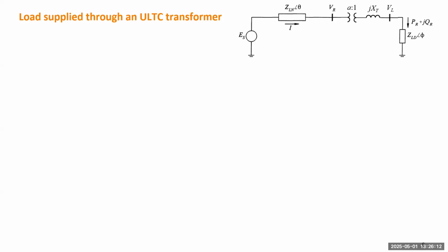Let me give you one example of how the load is controlled. Here I use an under load tap changing transformer. An under load tap changing transformer is a voltage controller, which means it can control voltage by changing the tap position. If you move the tap up on the secondary side, that will make the voltage on the secondary side higher.